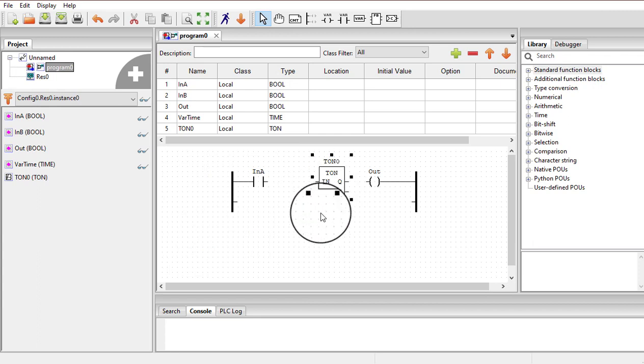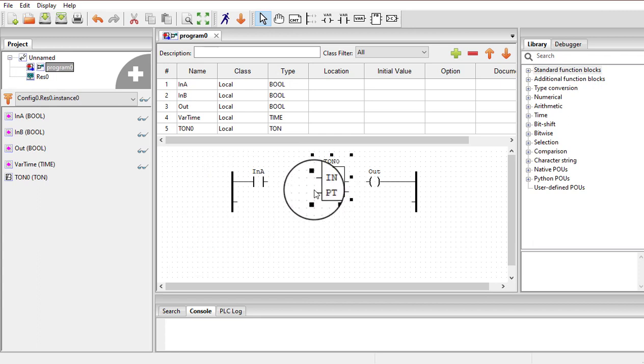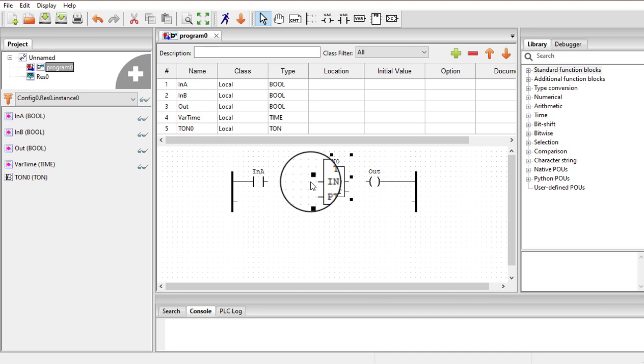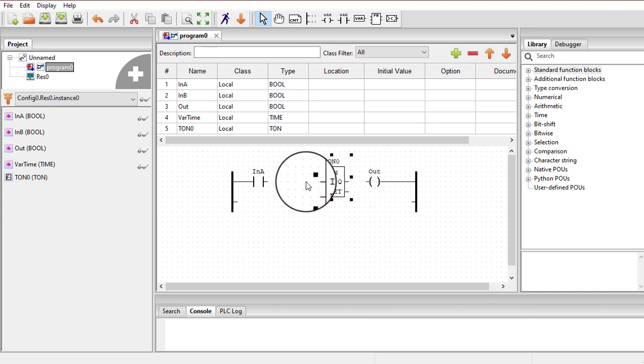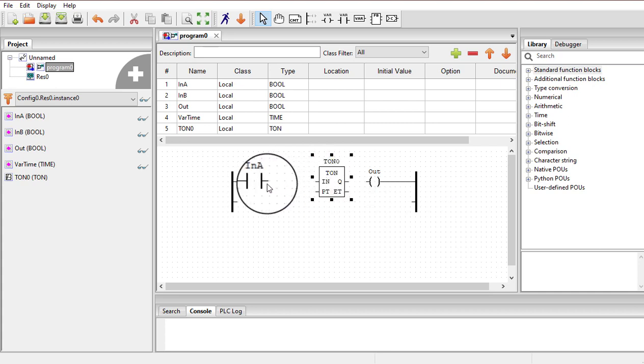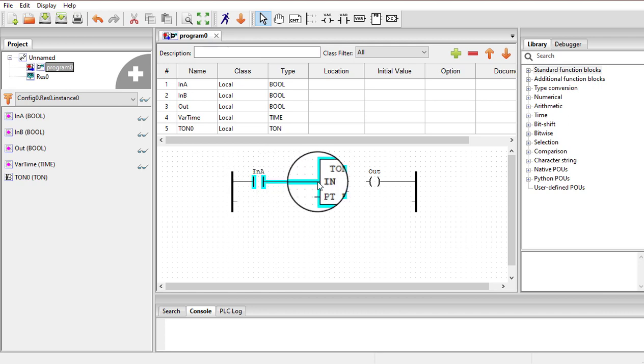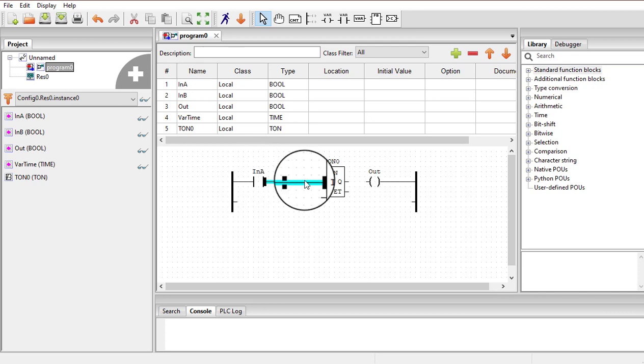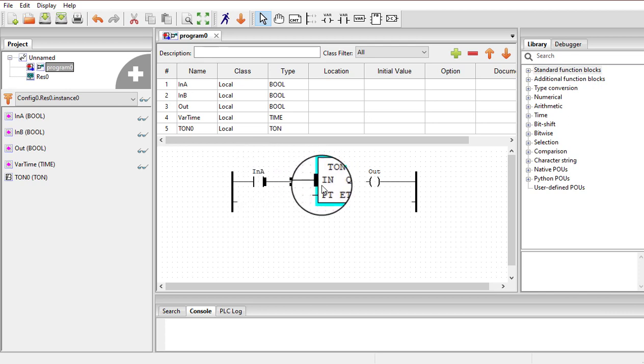This timer has four pins. The first one, the IN pin, is a Boolean type pin that requires a Boolean input. When that Boolean input is 1, this timer will be enabled and will start timing. When this pin receives a 0 the timer will be off. We can connect input A to this IN pin, so whenever the switch is on it will give 1 to the input pin and the timer will start.